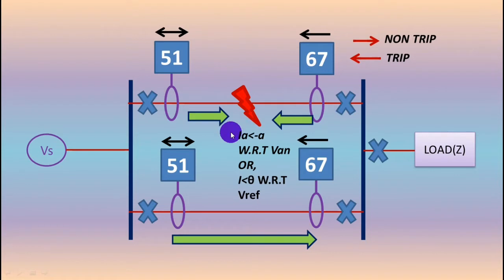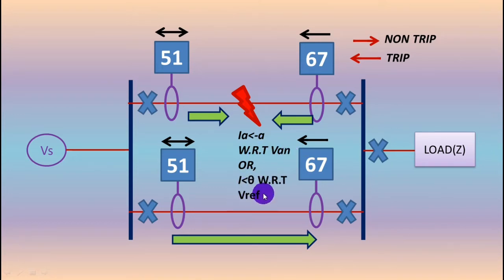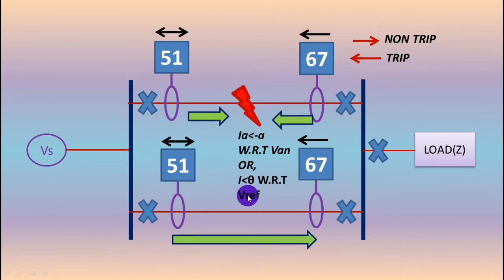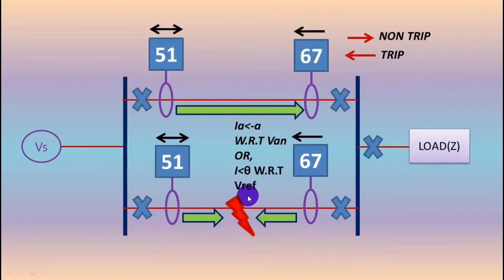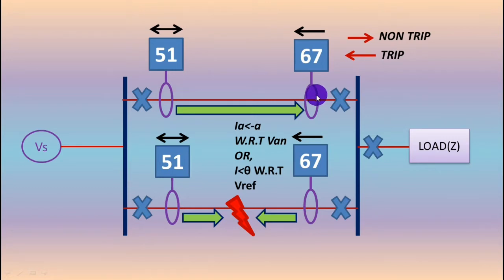Suppose this is a fault condition — these two lines are parallel. The fault current is I lagging angle theta with respect to V_AN, or I at angle theta with respect to V reference. This is the lagging angle and this is the leading angle. In the previous video I explained why the current leads the reference voltage if the fault occurs in this direction on this line. Here the direction is reversed, but the magnitude of the fault current and the phase angle relationship between current and voltage remains the same.